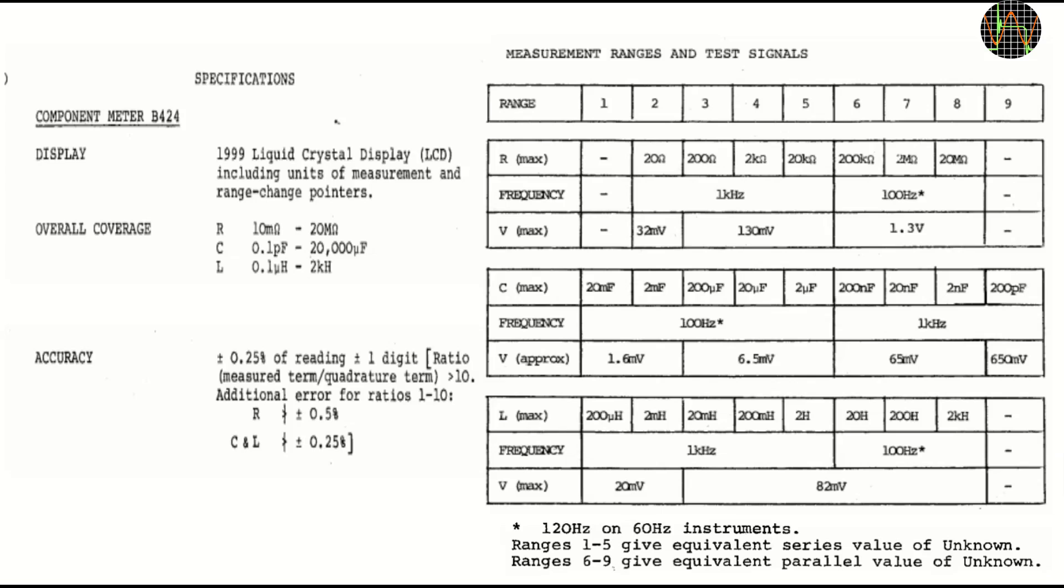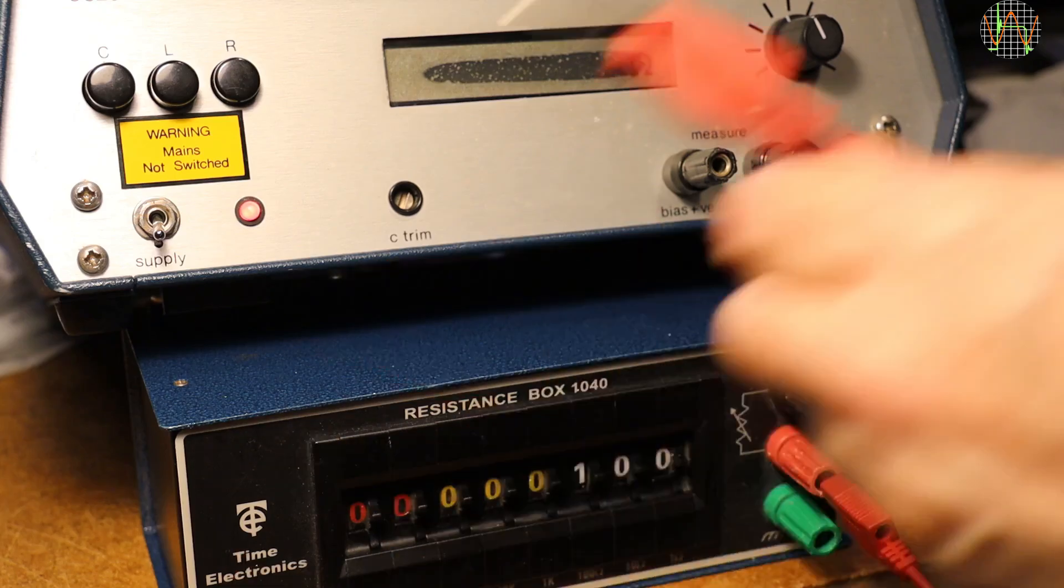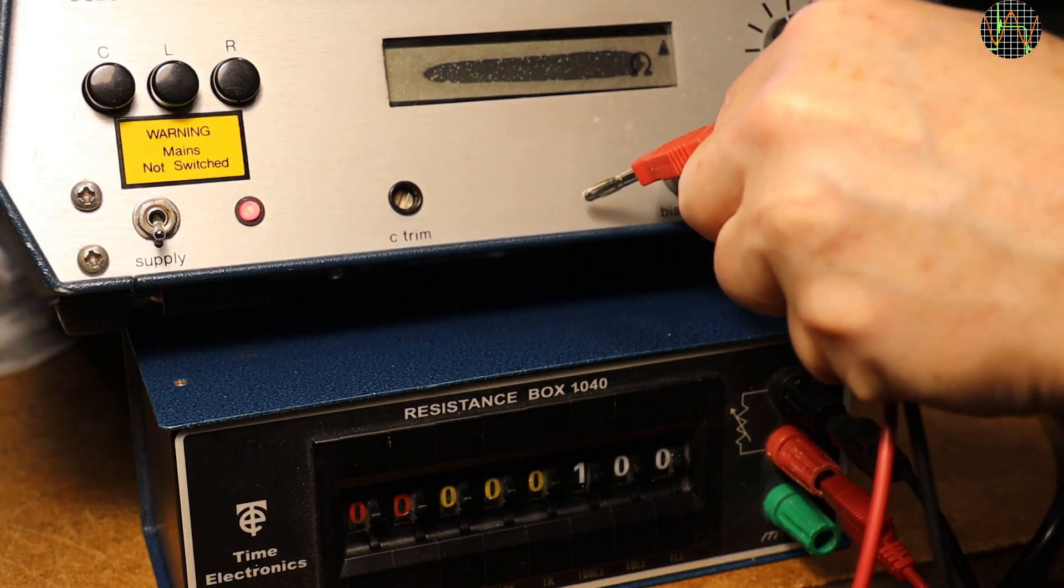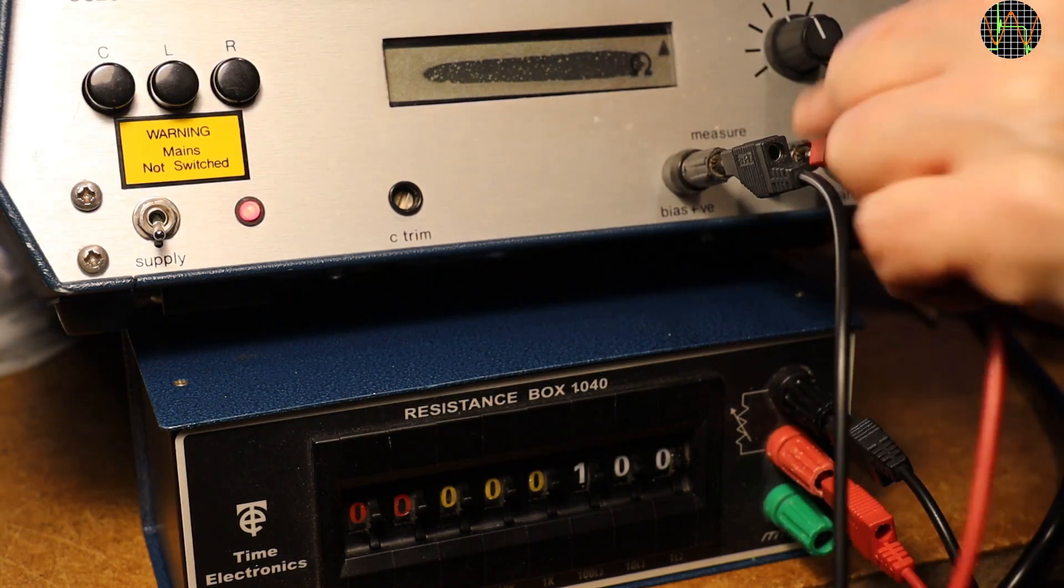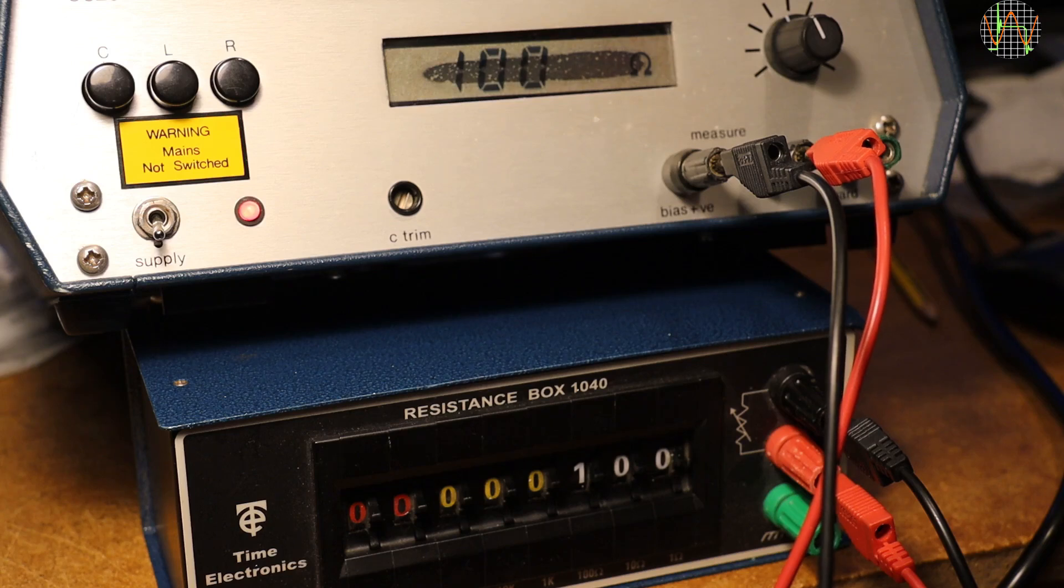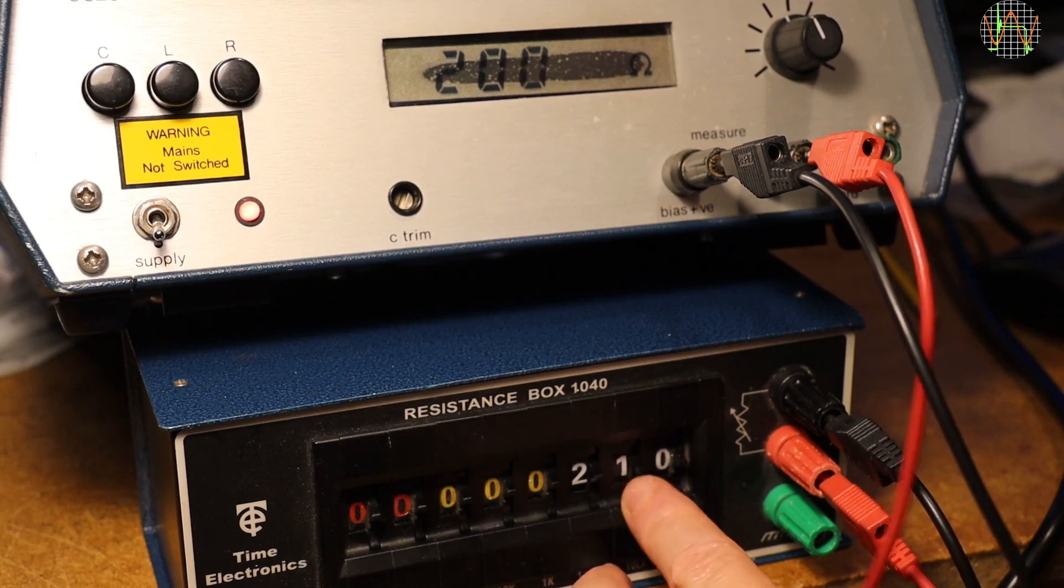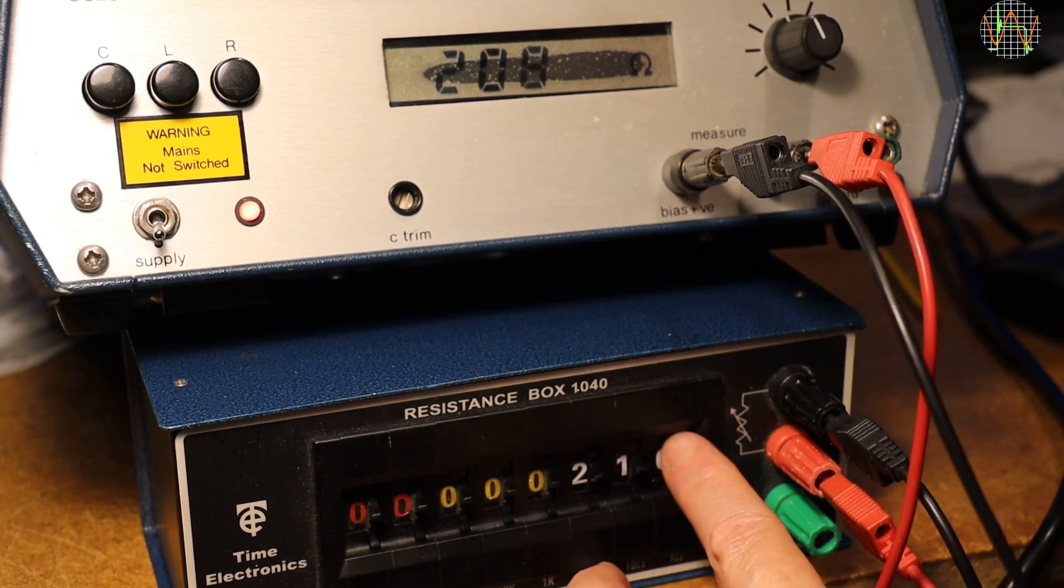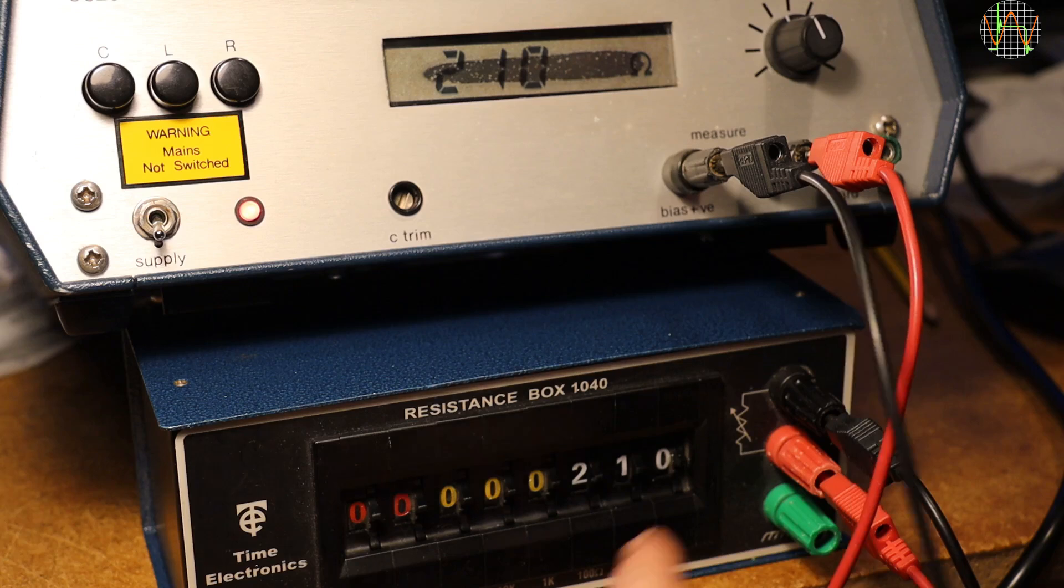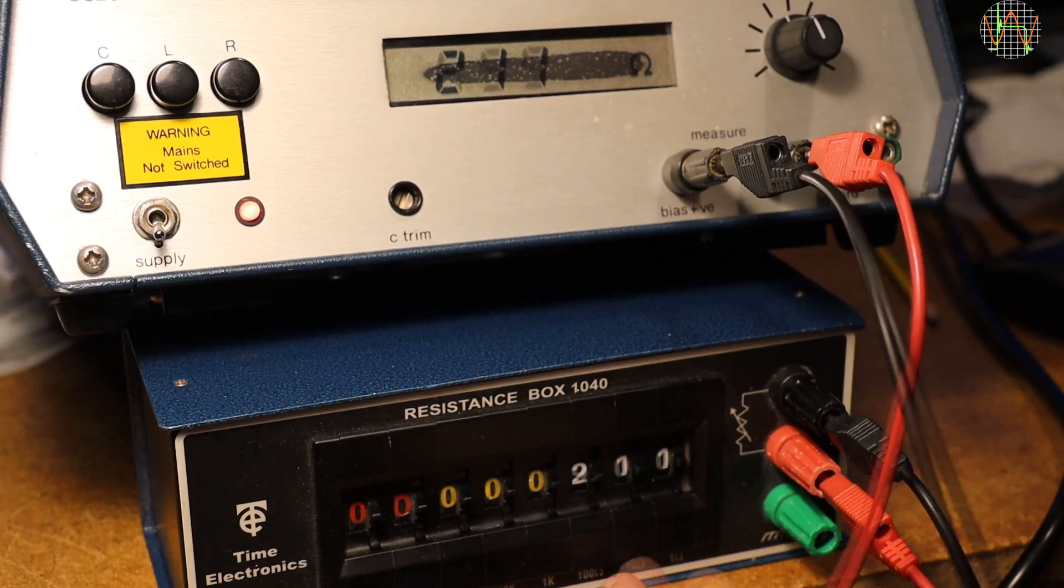It uses a sine wave of either 100 Hz or 1 kHz. For my first test, easiest is of course R or resistance and I connect a resistance decade box set to 100Ω to the B424. Despite the problems with the LCD, the display is somewhat readable, good. And changing to other resistance values on the decade box seems to work just fine.